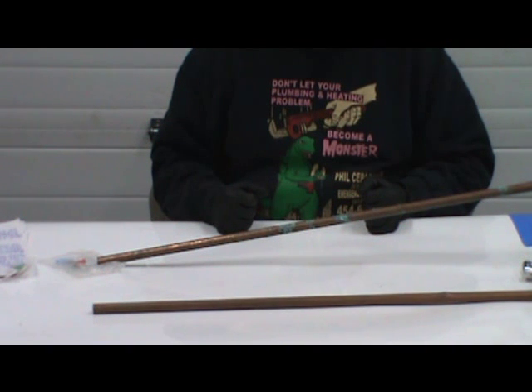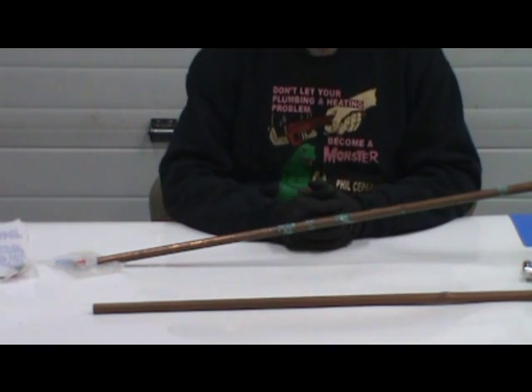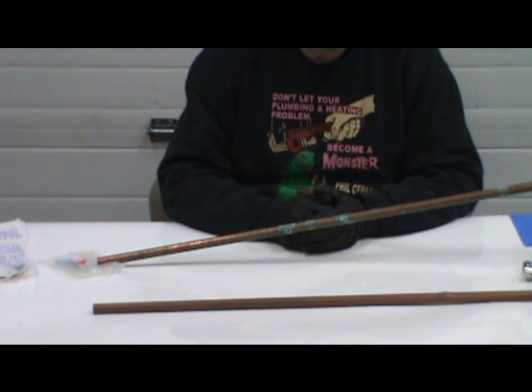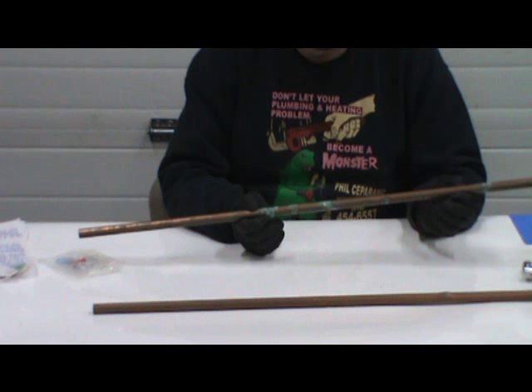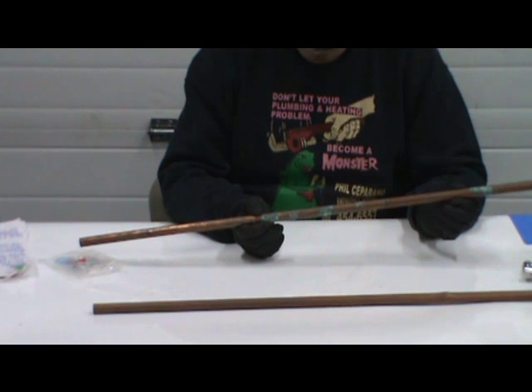Now this pipe is only 5 years old, and the pipe is not made in China. As far as I know, it's American pipe. So I had to rip the whole floor up and repipe it in PEX. And that's why now all I use is PEX. Anytime I replace any pipe, especially if they've had pinholes, I replace it in PEX. So that's why PEX is what should be used, okay? Because it can happen in a short amount of time.